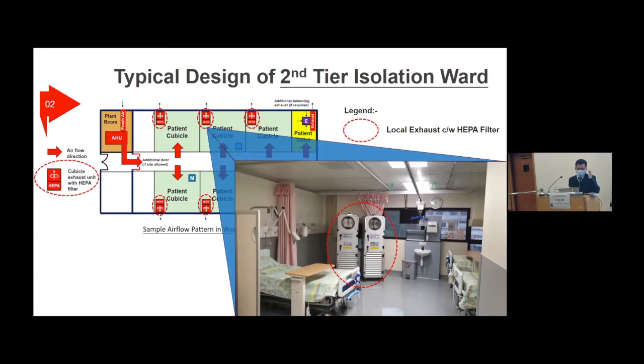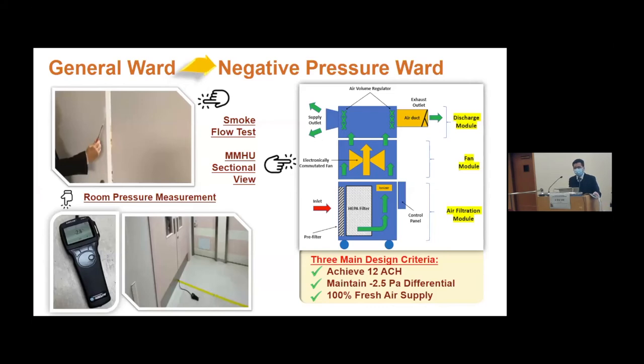This photo shows a typical configuration of a second-tier isolation ward with two sets of mobile HEPA purification units installed. The two units were installed for backup purposes. That is, one unit will maintain the operation in case the other one breaks down. Together with the necessary commissioning of the original ventilation system in the ward, the mobile HEPA purification unit was designed to allow the general wards to achieve an ACH greater than 12 and to maintain a pressure differential of negative 2.5 Pascal, which is equivalent to a standard airborne infection isolation ward.